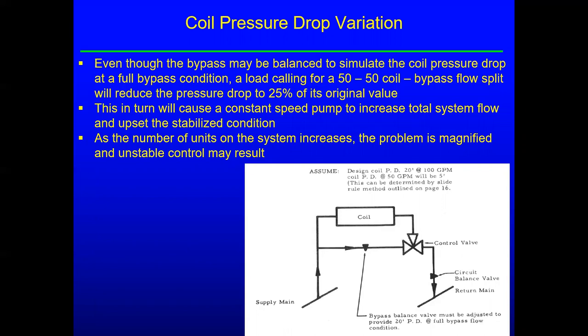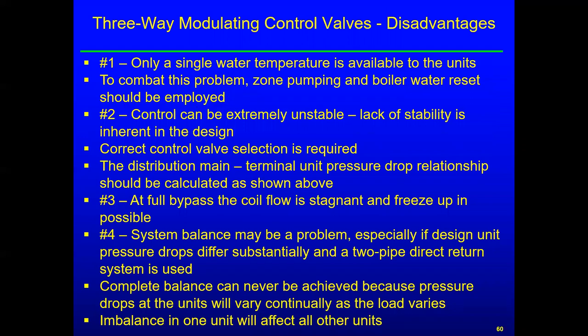That's probably what would happen. So these days, if a lot of coils go to the 50% position, instead of changing the flow in the header, we can simply adjust the speed of the pump and mitigate this. So we've got our three-way modulating control valves, our disadvantages. It could be that we only have a single water temperature available. So we would need to look at boiler water reset. It would probably be the solution to that.